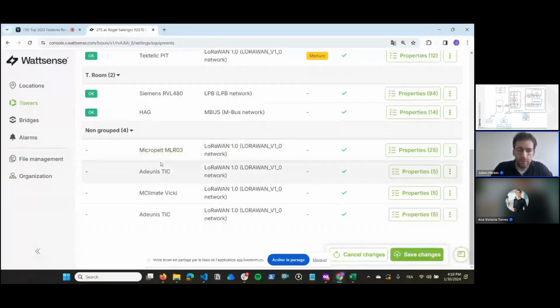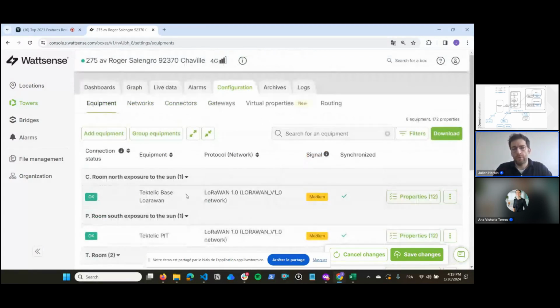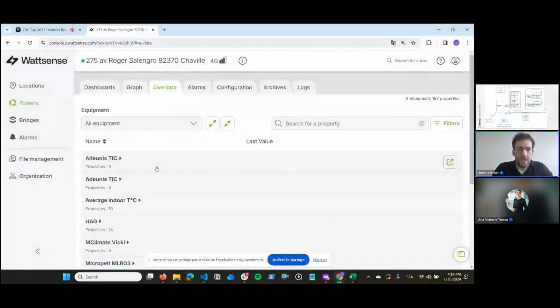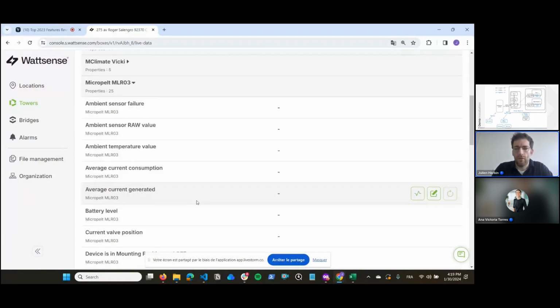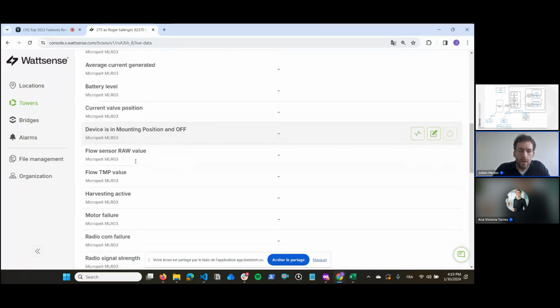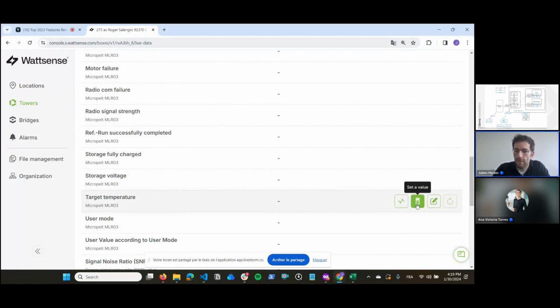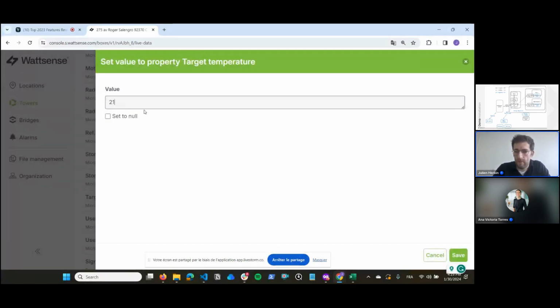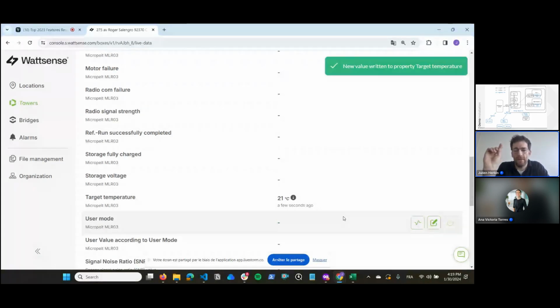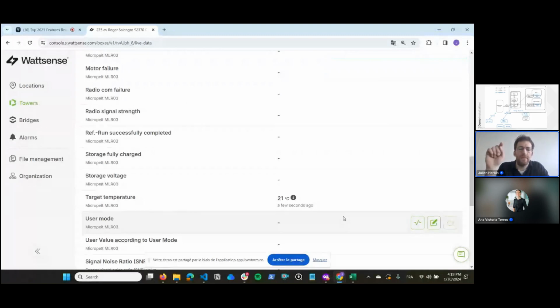This could be the case here with my two radiator valves, the MicroPelt and the mClimate. To make it easier to control equipment in your building, this year for very specific equipment you can now go under the live data view, select the corresponding equipment, here MicroPelt for example, and set the temperature of the valve directly. If I type 21 for 21 degrees Celsius and save it, and if my device was paired with the Connect box, we compute the downlink and automatically send it to the device. So you don't have to care which hexadecimal string you need to enter. You just pass 21 and it works.